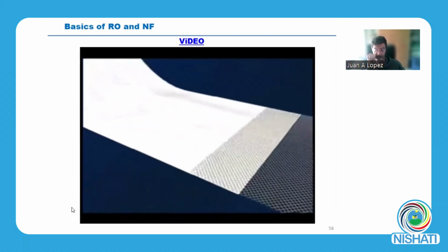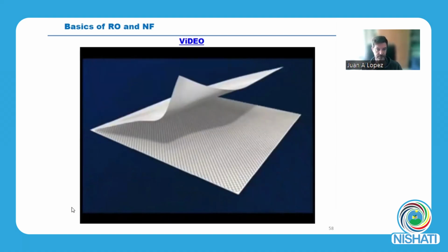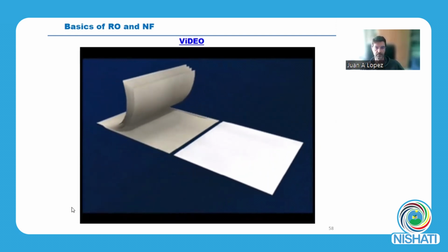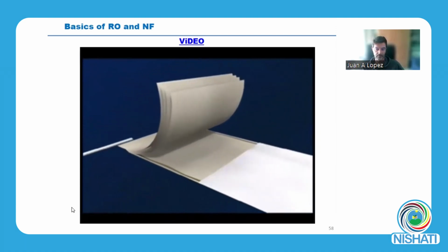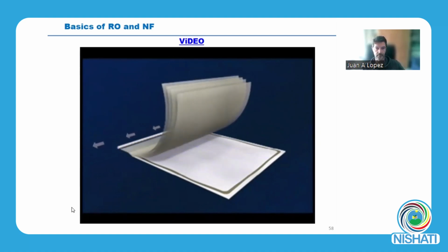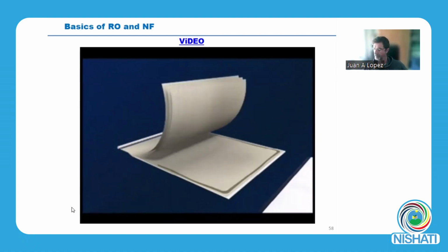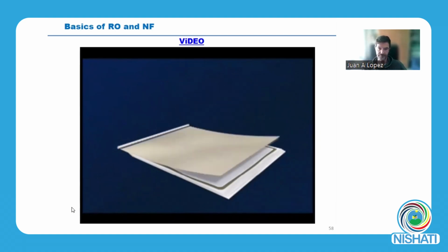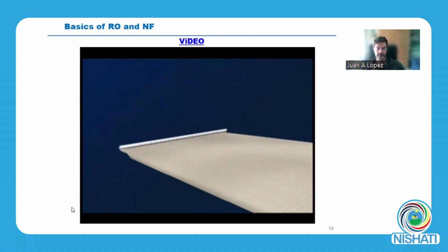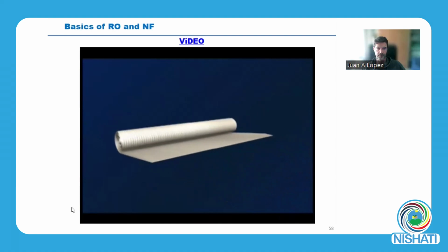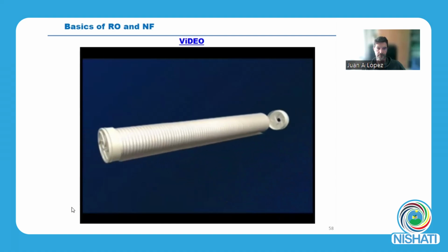And salt-rejecting skin. The combination of these three layers makes a durable membrane flat sheet that is used in each spiral wound element. The membrane flat sheet is then combined with a sheet of feed channel spacer. This provides turbulence and creates space between the membrane sheets to allow uniform flow of the water to the entire membrane surface. The leaves of membrane and feed channel spacer are then combined with a sheet of permeate spacer, which provides open flow channels for the permeate even under high pressure. The leaves are glued along each of the three exposed sides and then rolled around the core tube.